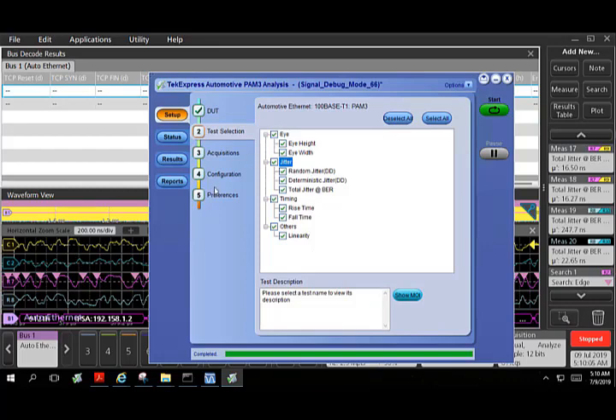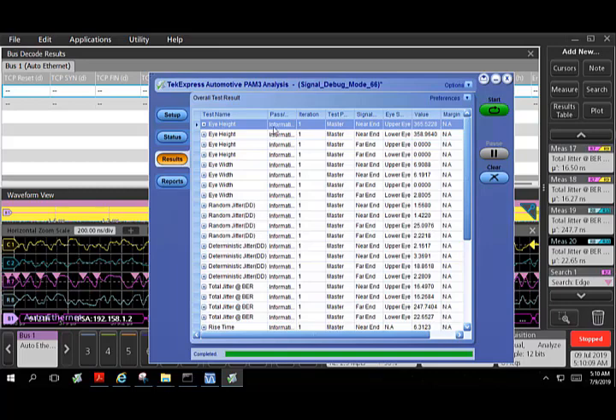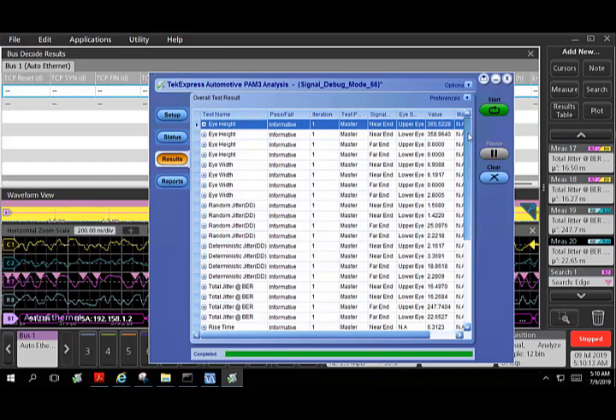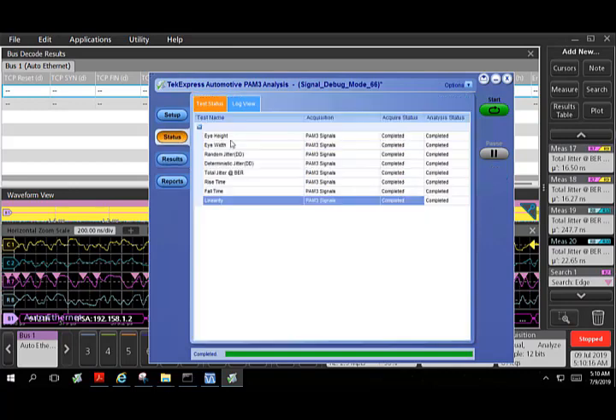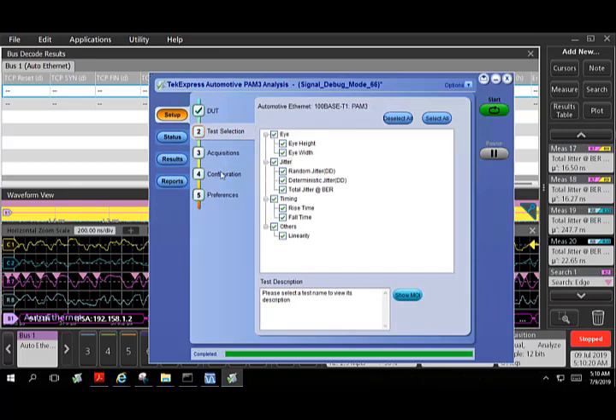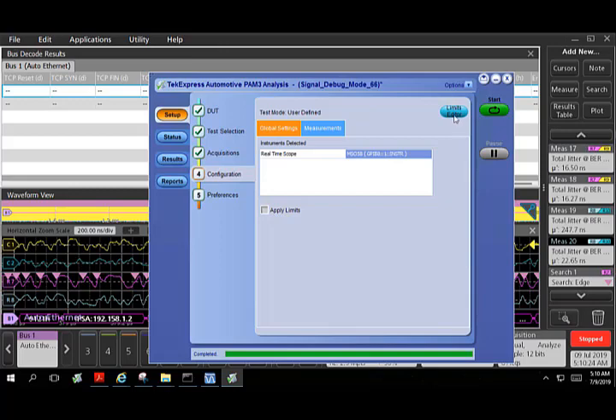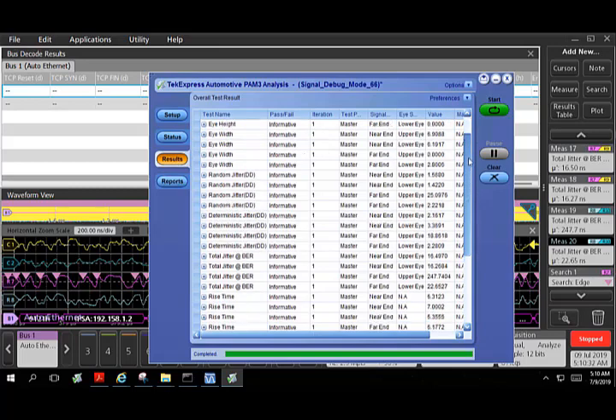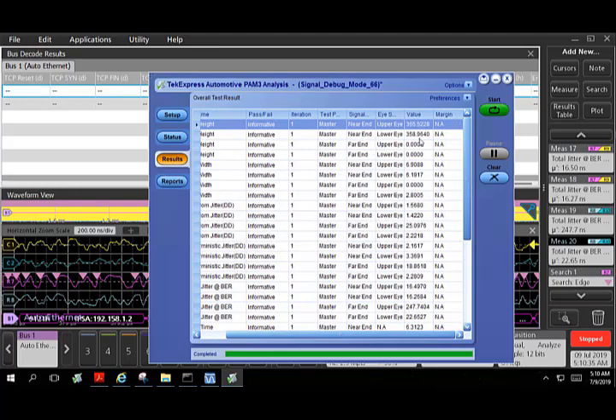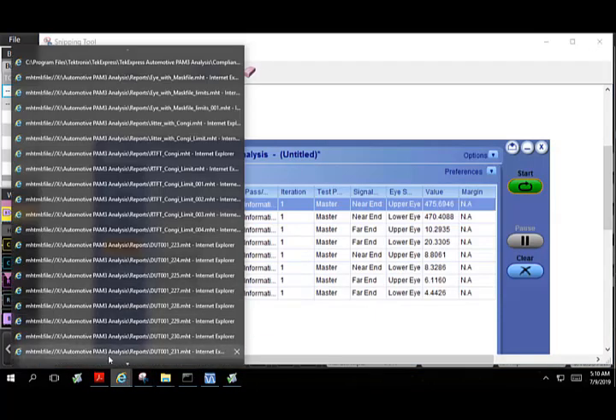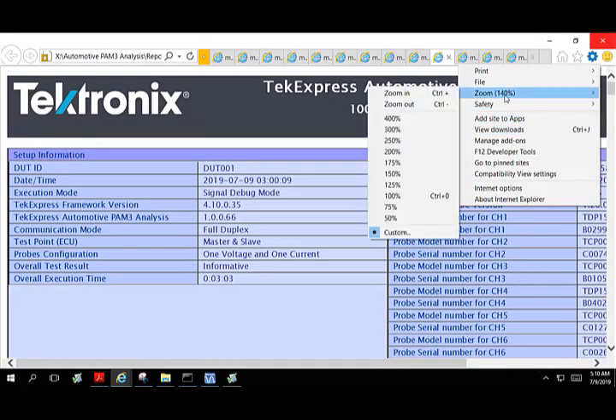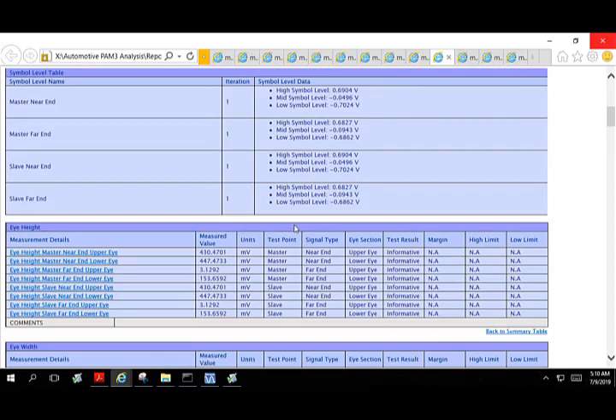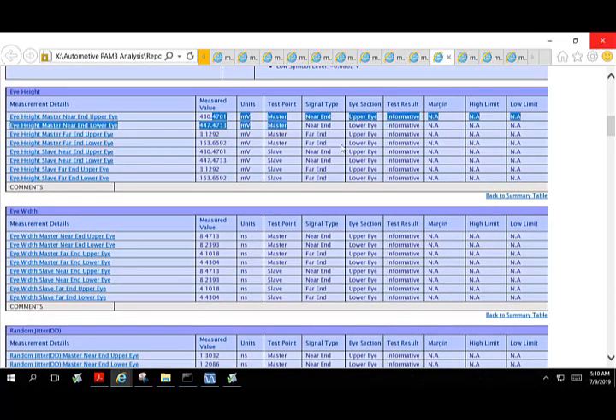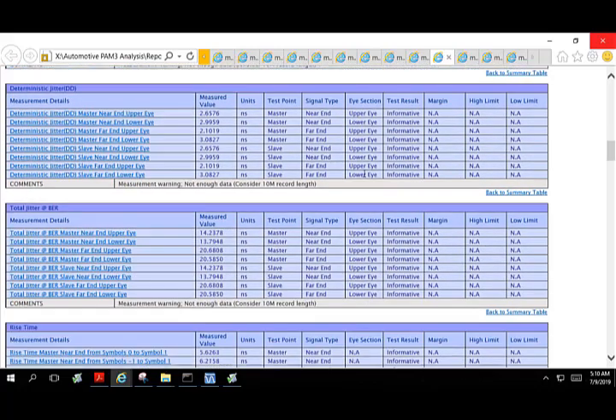So again, we are not going to run all these tests, but we have already run this test. In this case, this is the summary table. In this, we have defined user-defined limits, so the user can add all the limits here in the configuration panel. We have an editor to define and add the limits here, and then you can see the limits, so it will show you the measured value against those limits. We can also see the complete report of these measurements, which we make 100% so that we have better visibility. It gives you the scope model number, all the measurements it has performed. It gives you the limit and whether it is a pass or a fail against those limits.